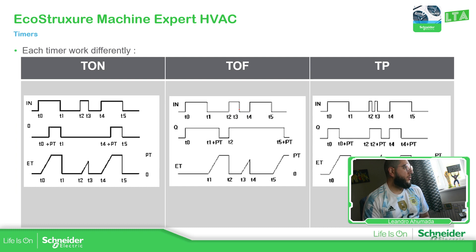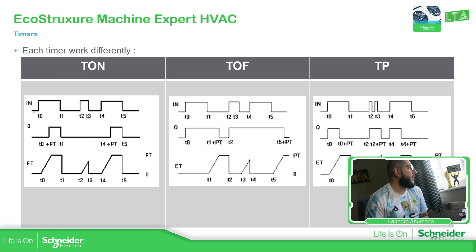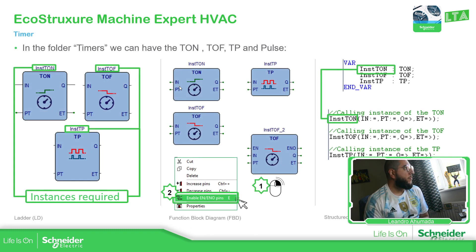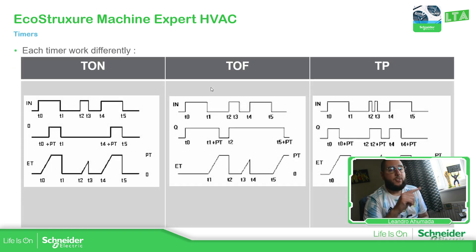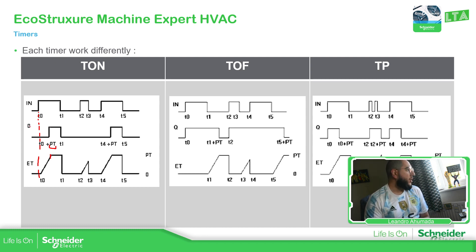So what these three timers do — the T-ON, retardo la conexión in Spanish. Basically you have the input, PT, and Q. The input is the signal you have. As soon as the signal goes true, the actual time starts increasing until it reaches the preset value PT. As soon as it reaches the PT, the output Q will be active, and it stays active as long as the input remains true. As soon as the input goes to false, it disconnects.